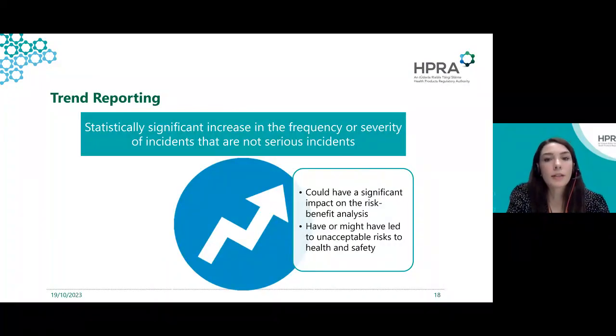Then trend reporting. This is a type of vigilance report where manufacturers have identified an increase in frequency or severity of incidents that are not serious incidents. So ordinarily these are incidents that are not reportable, but since their increase, they could have a significant impact on the benefit risk profile of the product or could lead to unacceptable risks to safety. They are to be submitted to the coordinating CA in the form of a trend report. So there is a form for that as well.